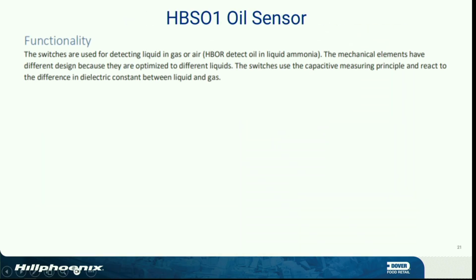HBSO1 sensor functionality. The switches are used for detecting liquid in gas or air; HBOR is for detection of oil in liquid, ammonia. The mechanical elements have different designs because they are optimized for different liquids, so the conductivity of liquids is different. Water is different than oil, different than CO2, right? CO2 is going to have a lower conductivity, right? Oil is more viscous. Hence the longer probes.